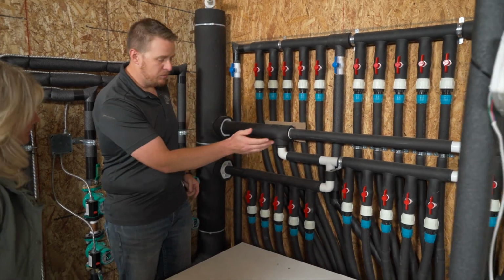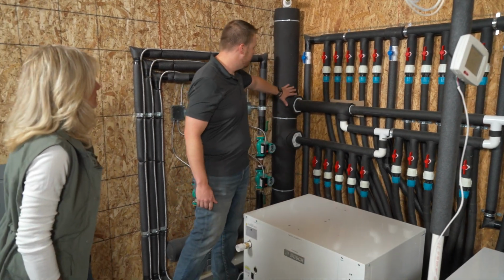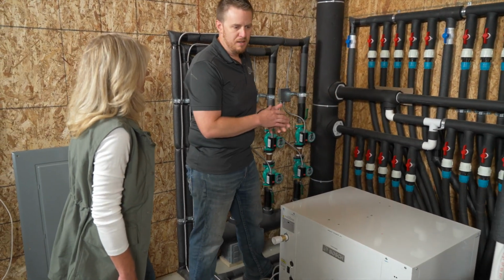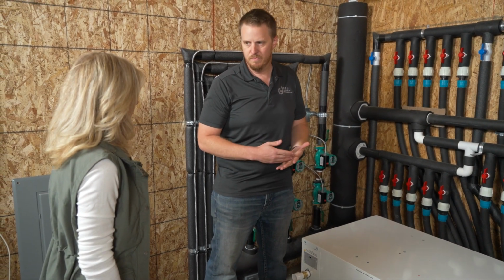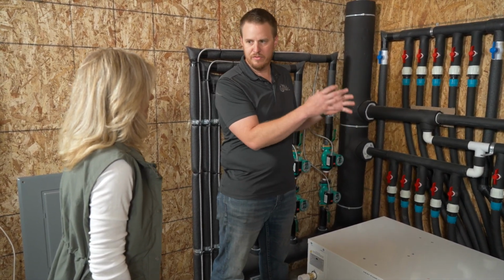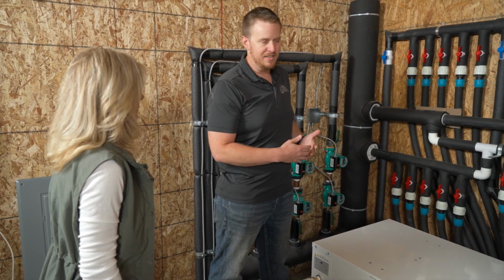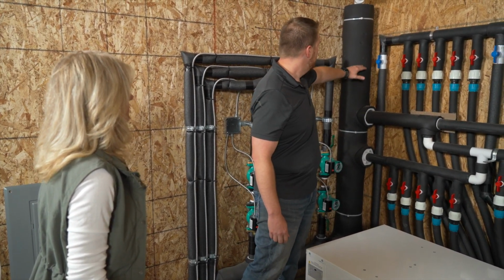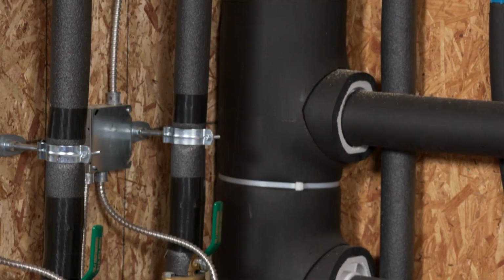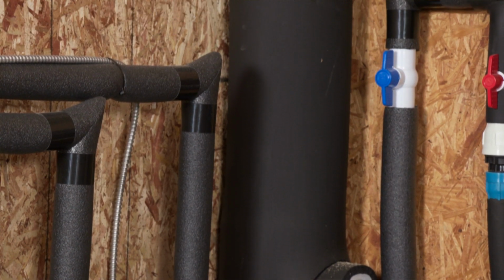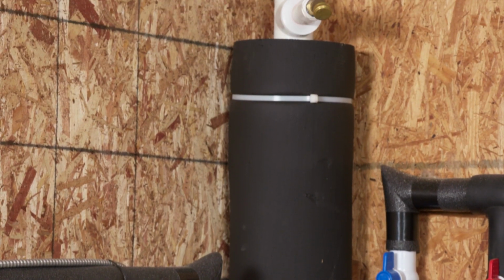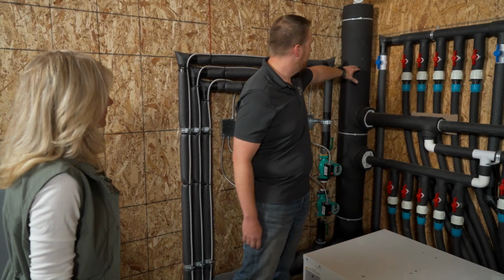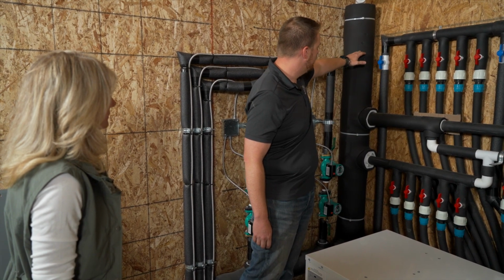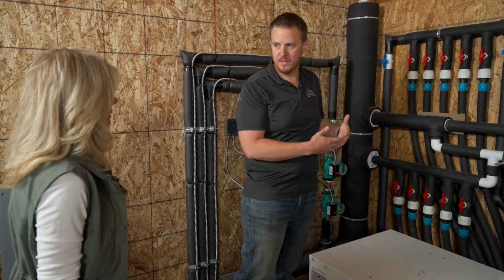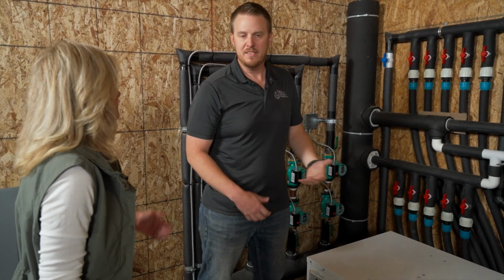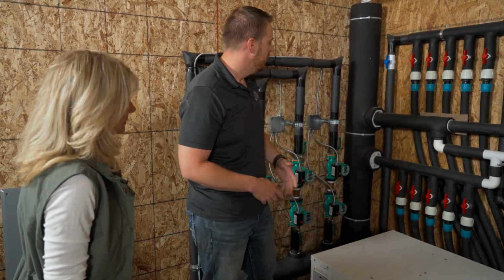So working our way from the manifold, we come over to the standpipe. This loop setup is a horizontal closed loop system, so it's on its own sealed system. There's antifreeze inside of here. We're not adding water to it constantly, and the water level typically sits right in this mid-level here. As that pipe in the ground starts to heat up and cool down, it is going to expand and contract slightly. So the volume of water inside that pipe will go up and down depending on what is going on with the loop. So that's like a reservoir of water, basically. It's a buffer tank for your ground loop, basically.